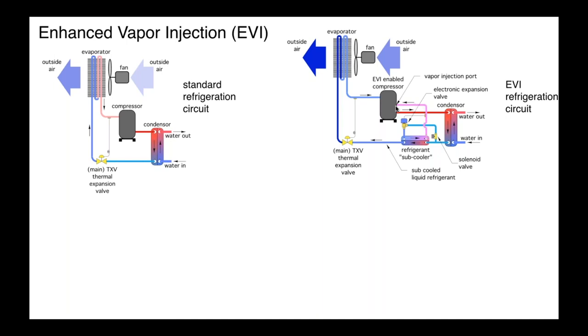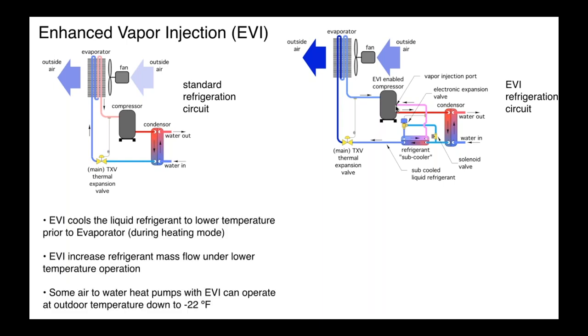Well, we've got to inject that into a special compressor. And there are compressors that are built, they're scroll-based compressors that have these gas injection ports built in. So they're cleverly designed so that that gas gets injected after the scroll set has actually closed off the inlet so that that gas cannot go backwards out of the compressor. And this does several things. Basically, it cools the liquid more before it gets to the TXV. It increases the mass flow of refrigerant going through the system, which under cold conditions increases the capacity of the machine. And it allows these air source heat pumps to get down to some very low outdoor ambient temperatures.